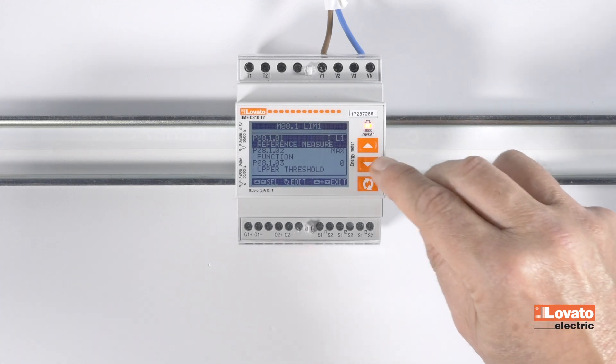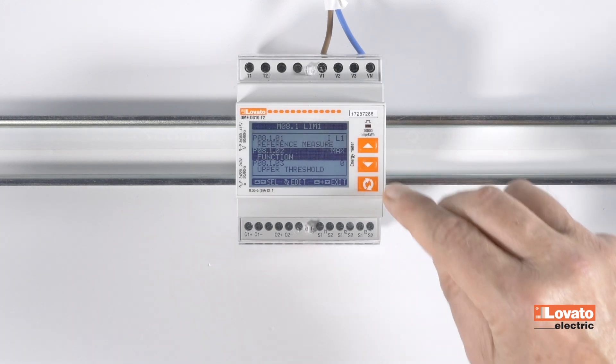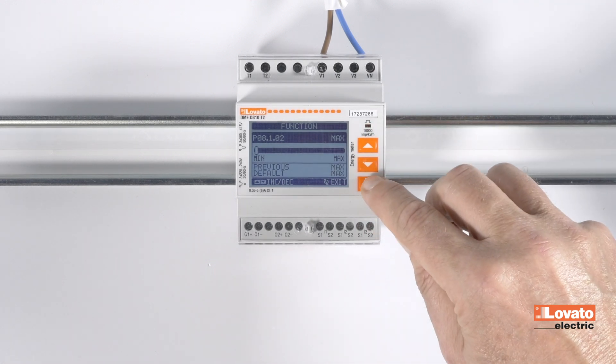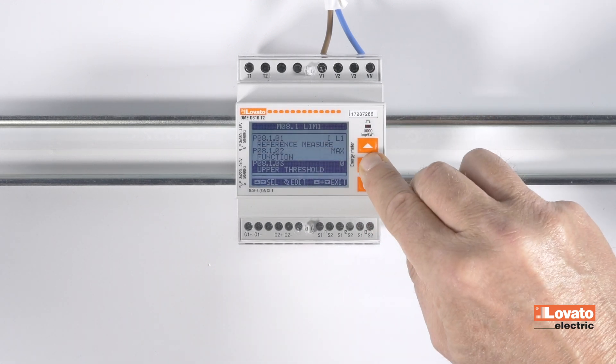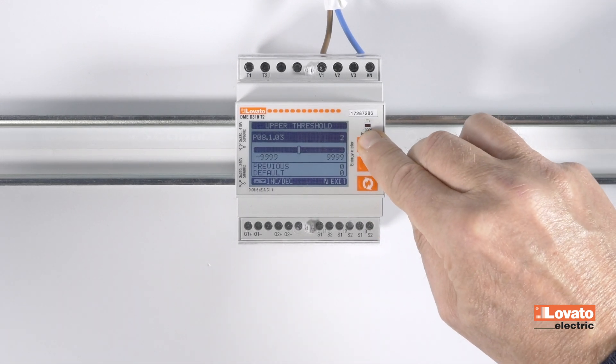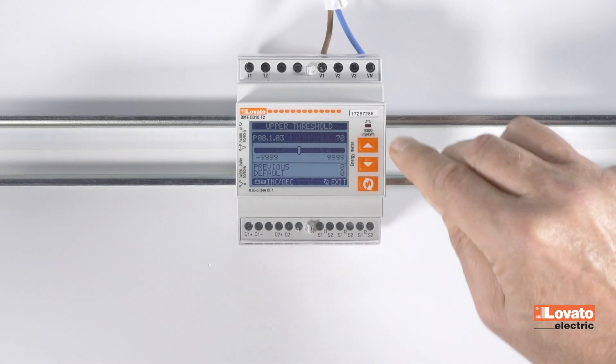Edit the function item, in this case, the maximum threshold. Now, enter the menu for the upper threshold. Current amperes, 70, with the up and down keys.